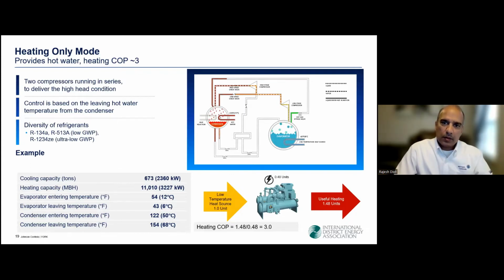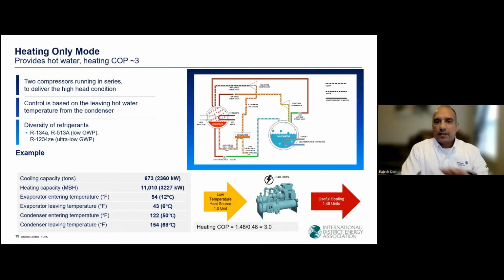It can be sewage wastewater, cooling tower water, can be coupled to a geo exchange field, river water, lake water, low grade industrial process water, or any sort of a low temperature waste heat. So the water that is cooled in the evaporator is simply returned to the source and is not used for beneficial cooling. Using the principle of compounding with two compressors operating in series, the heat pump overcomes the high head condition, delivering very high temperatures such as 170 degrees F or 77 Celsius, which is used for beneficial heating.